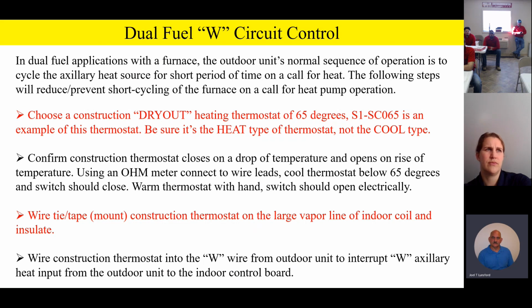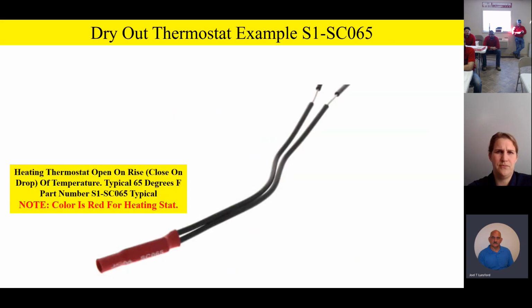So if you do a dual fuel, this is just a quick little overview. Take one of those little cartridge dry out thermostats. You've seen them, the sheetrockers use them all the time. It looks like this, that little dry out thermostat. And what you're going to do is break the W signal from the outdoor unit to the W signal on the furnace. You're going to take that little construction thermostat and break that W signal from the outdoor unit to the furnace, if you have a dual fuel.